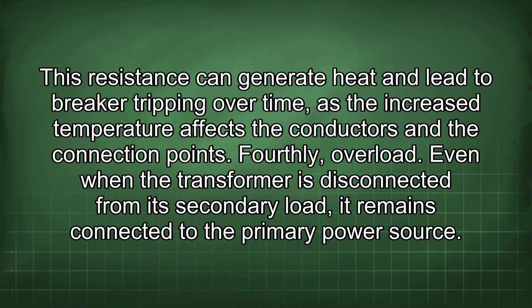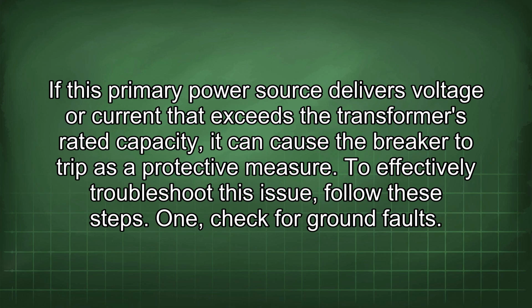Even when the transformer is disconnected from its secondary load, it remains connected to the primary power source. If this primary power source delivers voltage or current that exceeds the transformer's rated capacity, it can cause the breaker to trip as a protective measure. To effectively troubleshoot this issue, follow these steps.